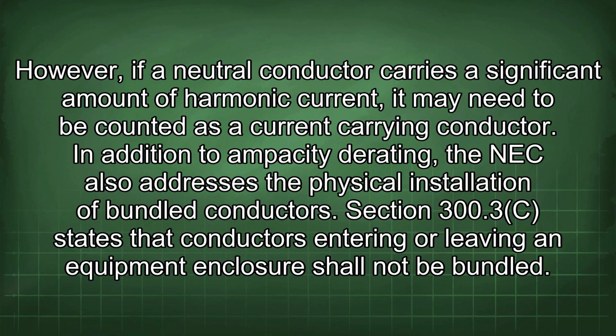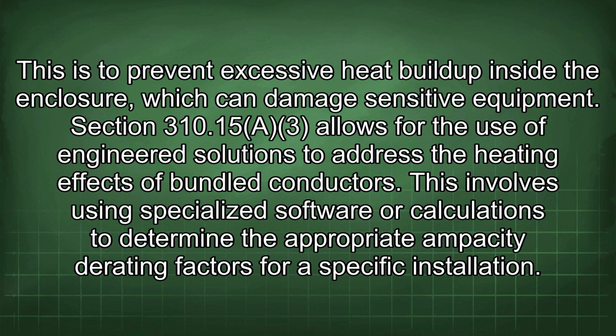However, if a neutral conductor carries a significant amount of harmonic current, it may need to be counted as a current-carrying conductor. In addition to ampacity derating, the NEC also addresses the physical installation of bundled conductors. Section 300.3(C) states that conductors entering or leaving an equipment enclosure shall not be bundled. This is to prevent excessive heat buildup inside the enclosure, which can damage sensitive equipment.